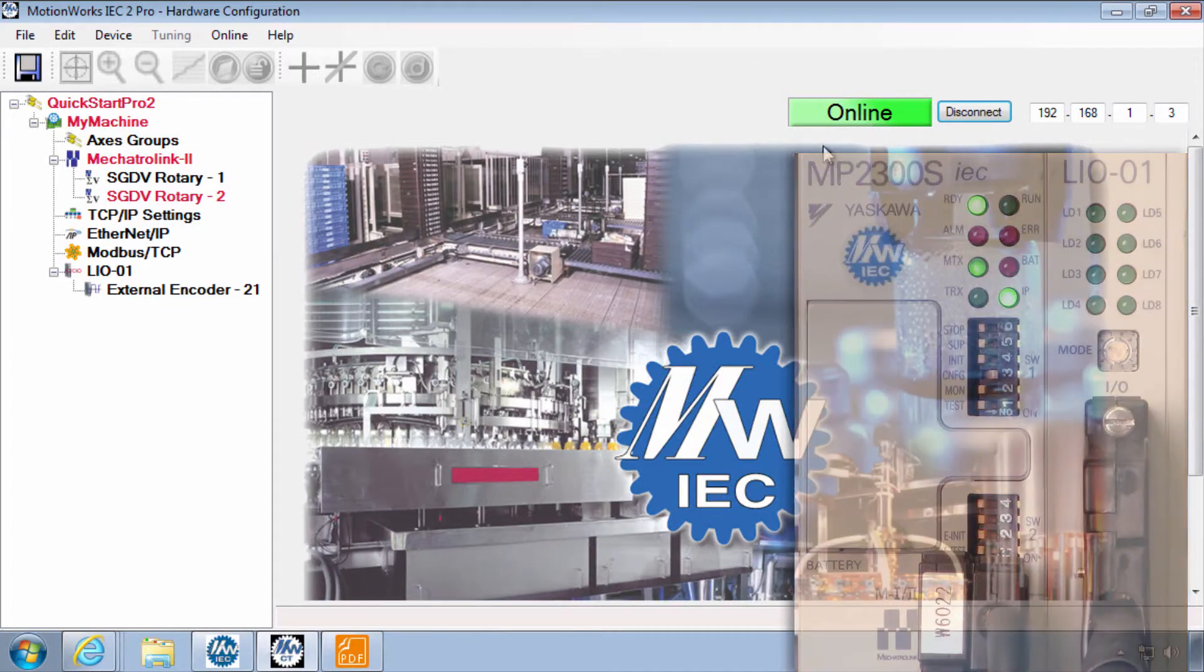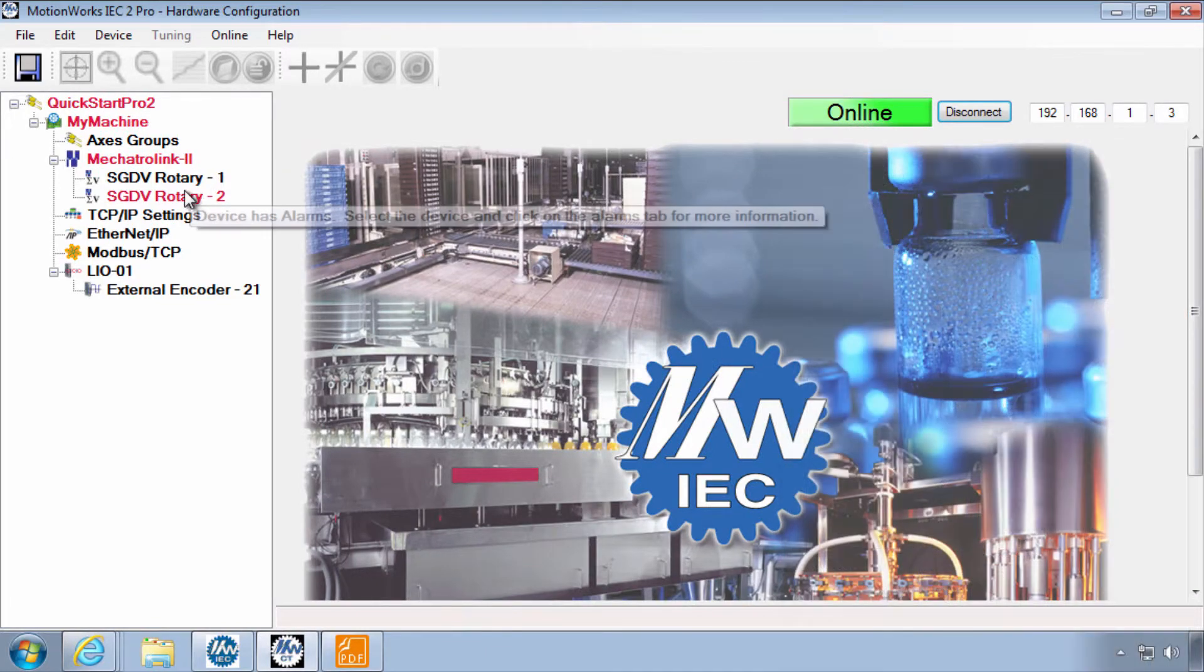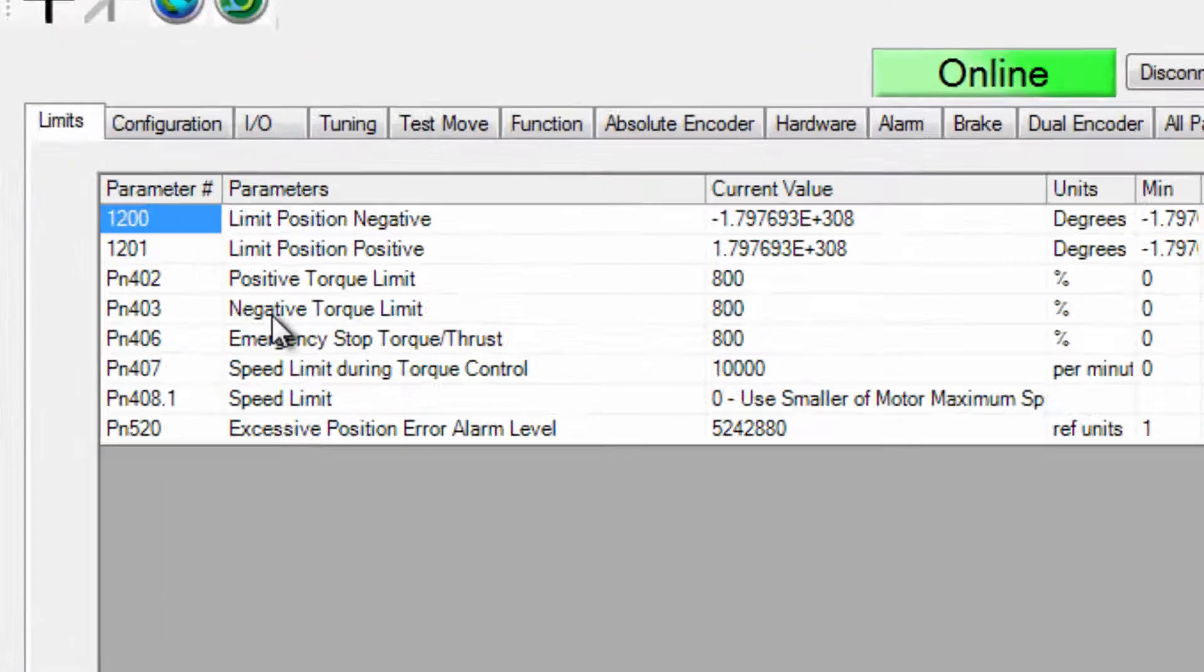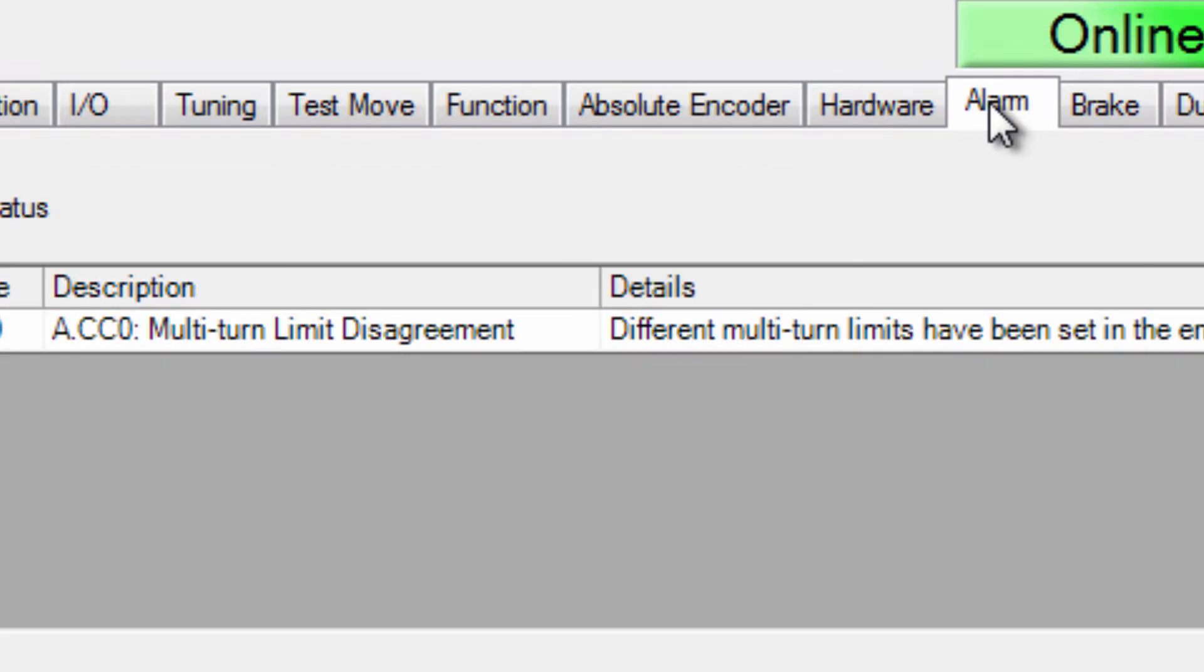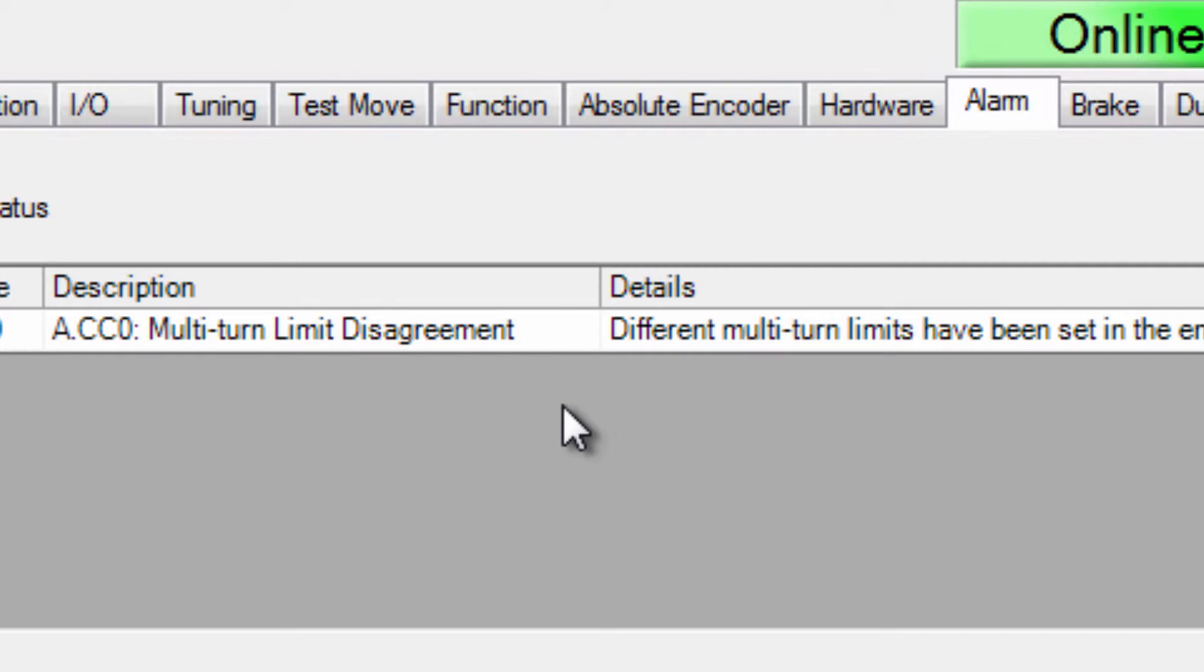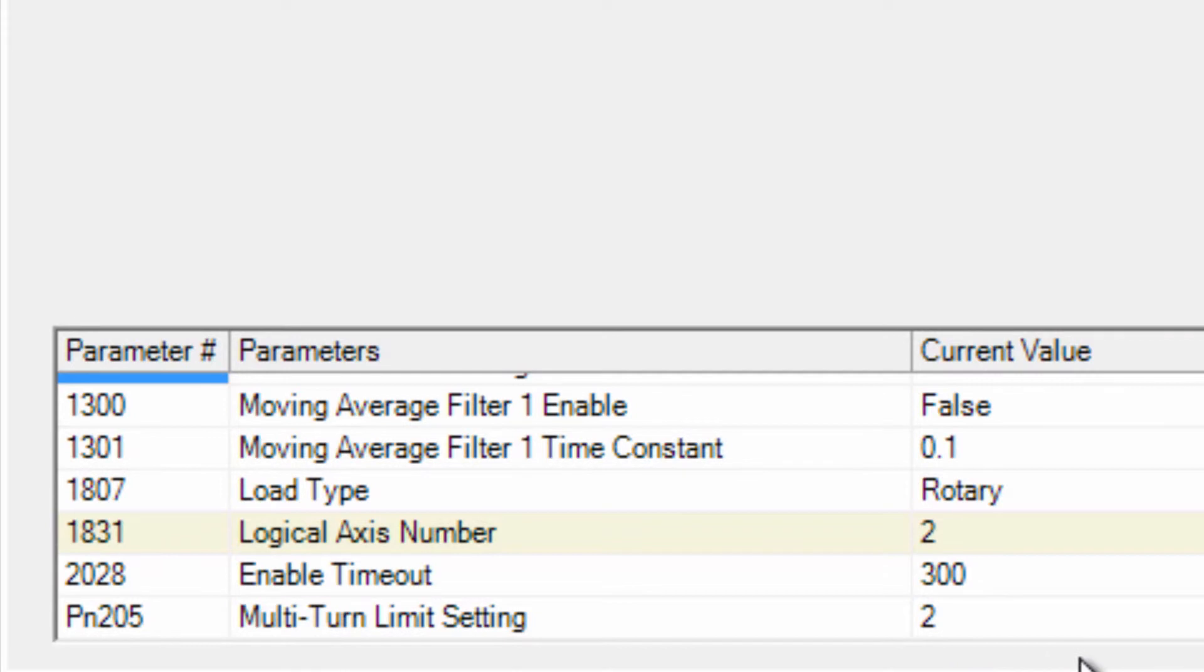Online now I can see that axis number 2 under the alarm tab has an alarm for multi-turn limit disagreement. Alarm ACC0. To clear this alarm we need to send that setting here 2 for the multi-turn limit into the encoder.